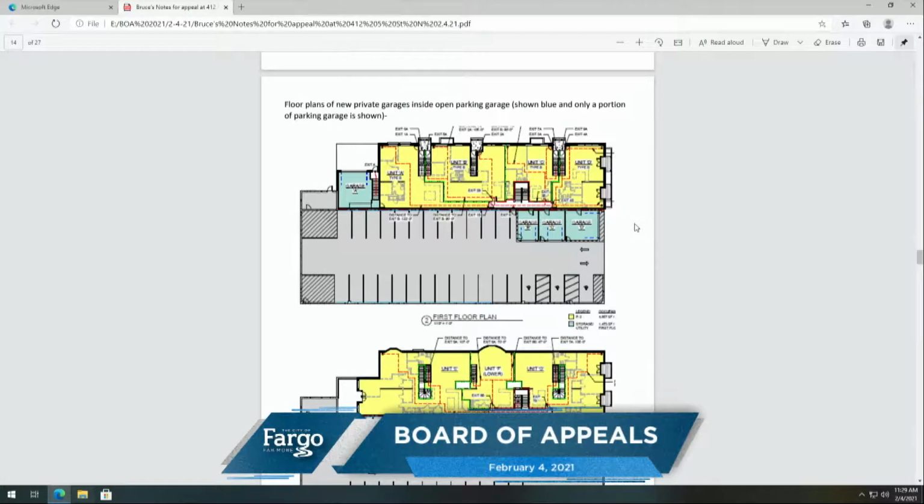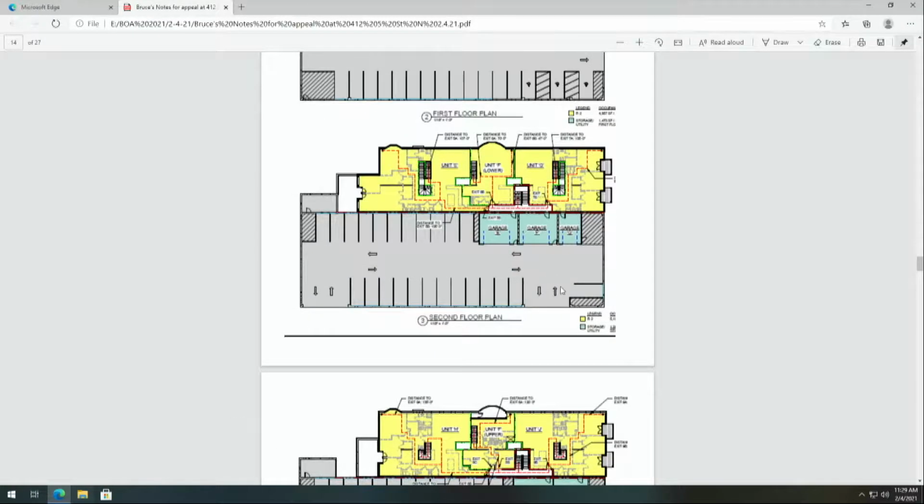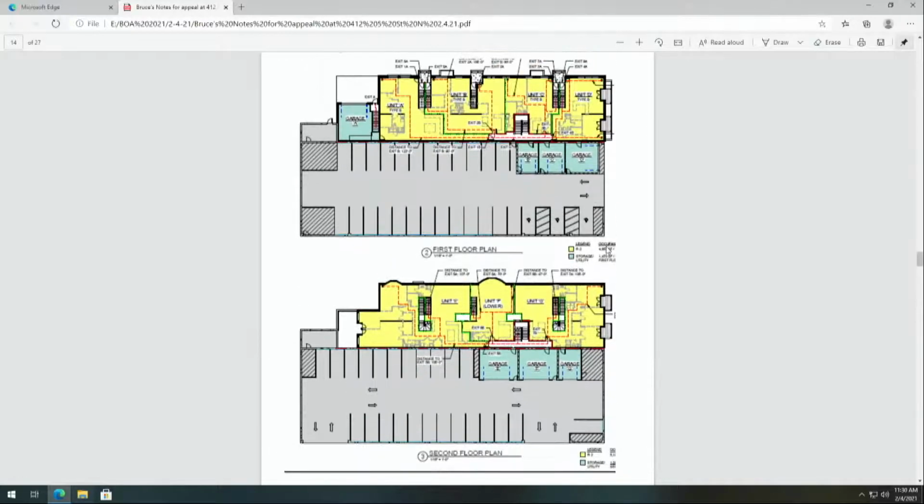If I were to ask a clarification, if I look at the first floor plan, the one on the east side, garage D, there's an opening on that east side. So let's say we meet that horizontal assembly requirement between first and second floor, but the opening of garage D on first floor, let's just hypothetically say there's a car fire in there. That horizontal assembly does nothing to keep that fire from going vertical. That be appropriate? Well, you've got unprotected opening separation requirements.